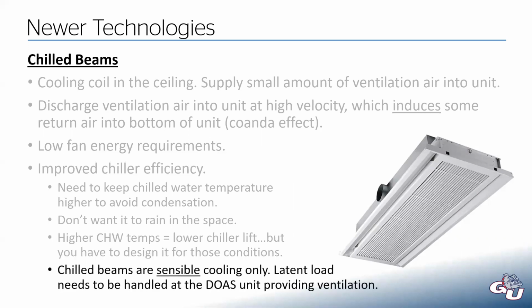And so these beams are sensible cooling only, which means the latent load that's going to be produced by all of the people in the space has to be picked up at the DOAS unit. So these are typically paired up with large direct outside air systems. And at those units, that's where we have to have some additional cooling to handle that latent load so that we don't end up building up humidity and moisture in the room.